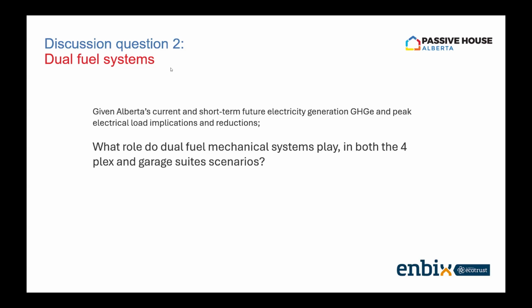I wouldn't look at trying to modulate a very small furnace. I'm going to disagree and say it's a problem of design and equipment, because I could do 4 furnaces in this fourplex and not have any ventilation issues through a -40 winter. We can discuss afterward how to make that happen. On new builds, I'd agree that the connection fee and running the gas line service isn't worth it. We can get our envelopes to a point where we don't need gas at all. We have a very efficient envelope and do it with heat pumps and very little electric heat, and this fourplex is going to be a great example of that.